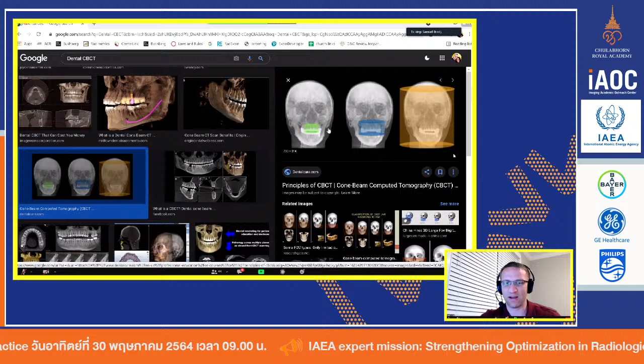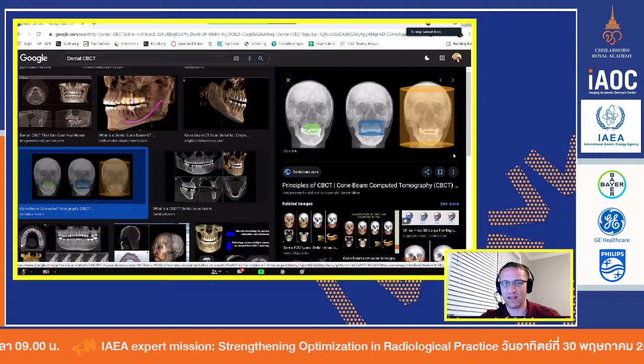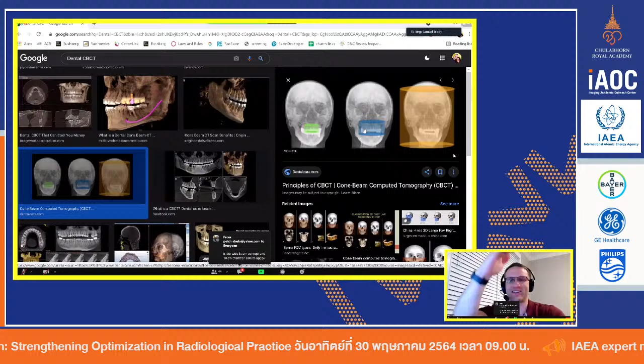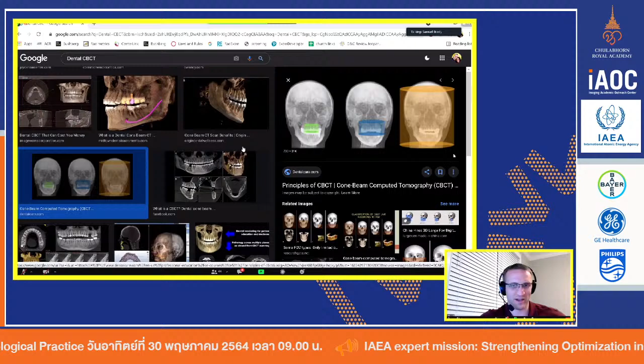Right here, you can see this blue, green, blue, and how it changes the area in the front or maybe the sides. That said, this is actually a bad graphic because you can't collimate this way. It's always going to be the same size. You would never be able to do that. So this is a bad graphic. I don't even know what they're doing there. So the answer is you'll never have a DLP. No DLPs in this.